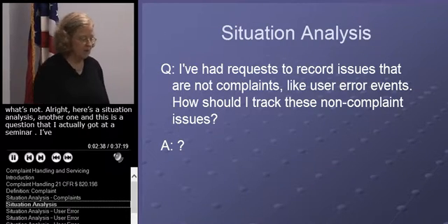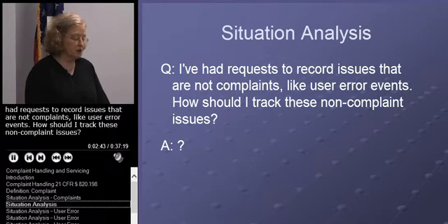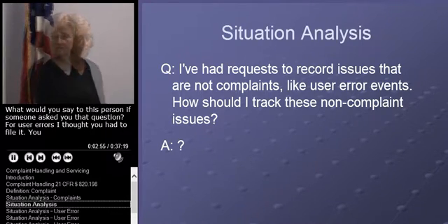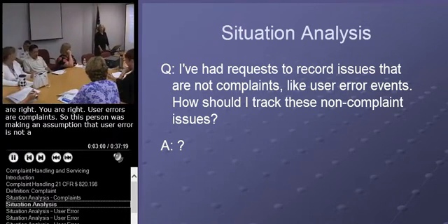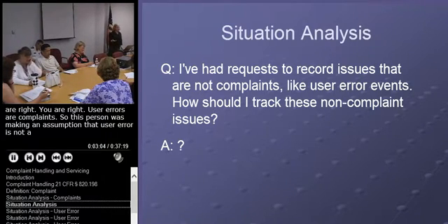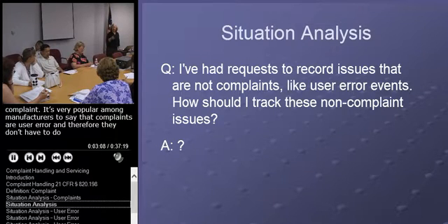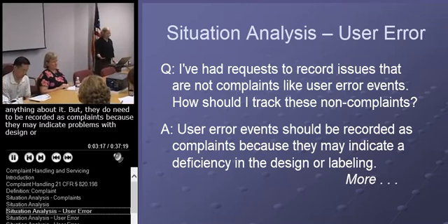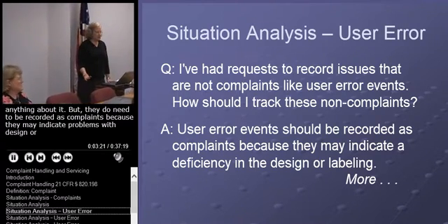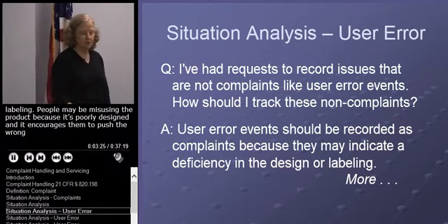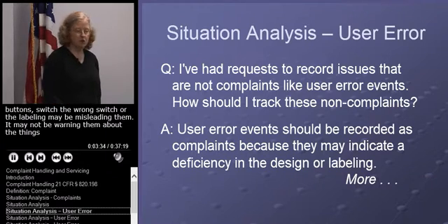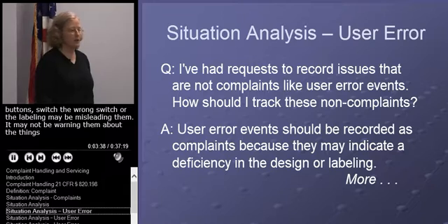Here's another situation analysis — a question I actually got at a seminar: 'I've had requests to record issues that are not complaints, like user error events. How should I track these non-complaint issues?' Well, user errors are complaints. This person was making an assumption that user error is not a complaint. It's very popular among manufacturers to say complaints are user error and therefore they don't have to do anything about it. But they do need to be recorded as complaints because they may indicate problems with design or labeling. People may be misusing the product because it's poorly designed and it encourages them to push the wrong button, switch the wrong switch, or the labeling may be misleading them or not warning them about things they should not be doing.